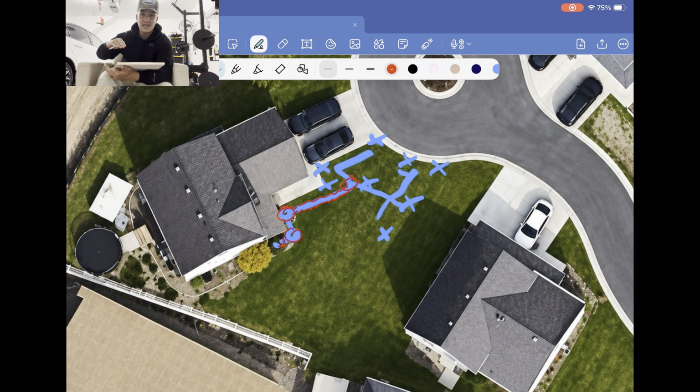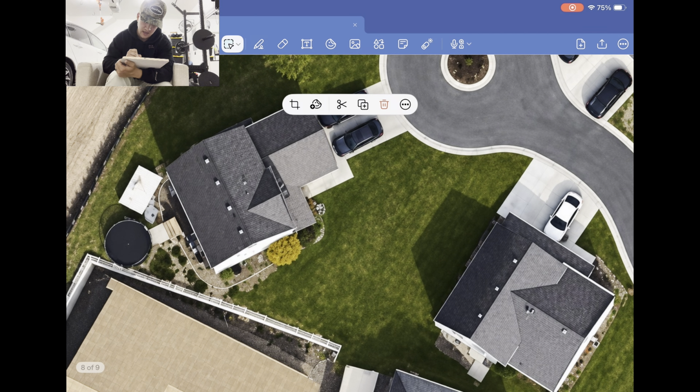If we go up and then down, all we're getting is friction loss. We're not actually getting the head change, if that makes sense, because it evens out. But every movement adds some friction loss. And there are friction loss charts that manufacturers make that we can access and use for calculations of system designs. But generally, in a small residential sprinkler system, friction loss is going to be pretty negligible.